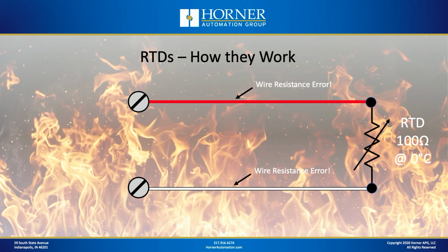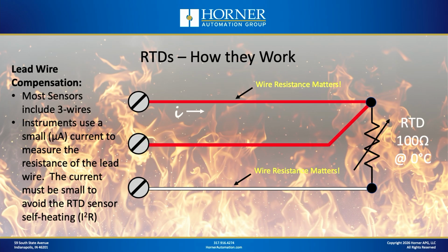Okay, now one thing you do have to keep in mind with RTDs is that the wire that is connected between the RTD sensor itself and your PLC or other measuring instrument, if there's enough resistance in that wire, it can cause an error, because what you want to measure is the resistance at the hot junction or where the probe is located. You don't want the total resistance including the wire, because that's going to give you an error. So you have to compensate for that wire resistance error.